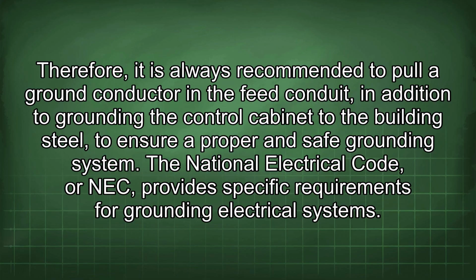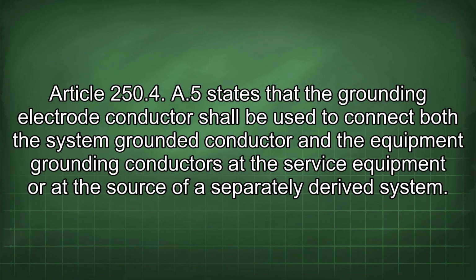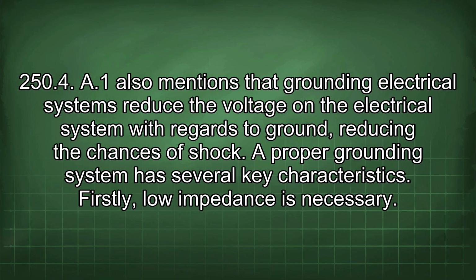The National Electrical Code, or NEC, provides specific requirements for grounding electrical systems. Article 250.4(A)(5) states that the grounding electrode conductor shall be used to connect both the system grounded conductor and the equipment grounding conductors at the service equipment or at the source of a separately derived system. 250.4(A)(1) also mentions that grounding electrical systems reduce the voltage on the electrical system with regards to ground, reducing the chances of shock. A proper grounding system has several key characteristics.